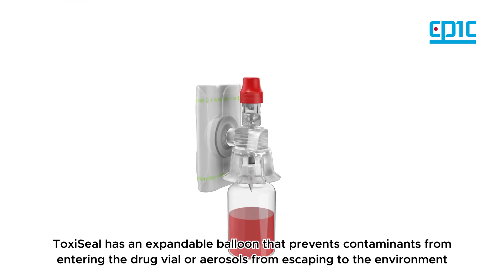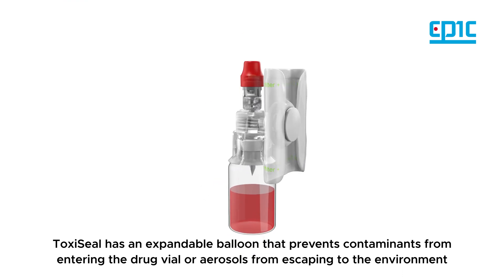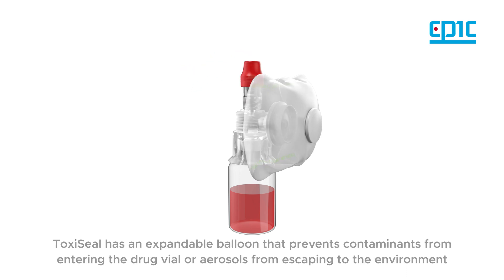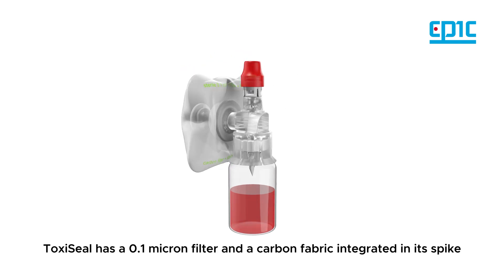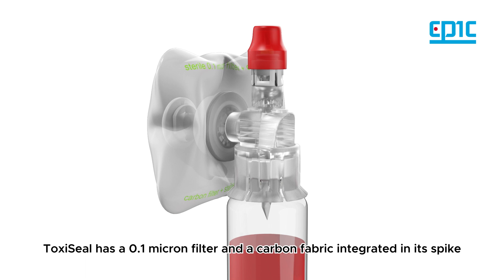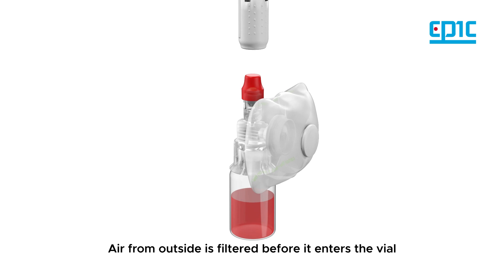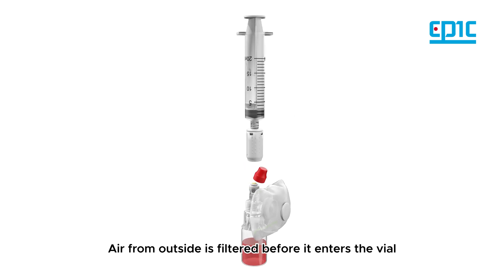ToxiSeal has an expanded balloon that prevents contaminants from entering the drug vial or aerosols from escaping to the environment. It also has a 0.1 micron filter and a carbon fabric integrated in its spike, so air from the outside is filtered before it enters the vial.